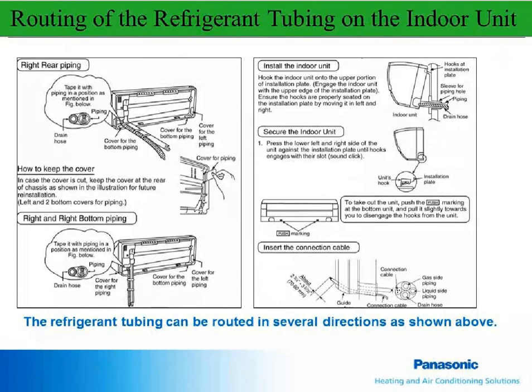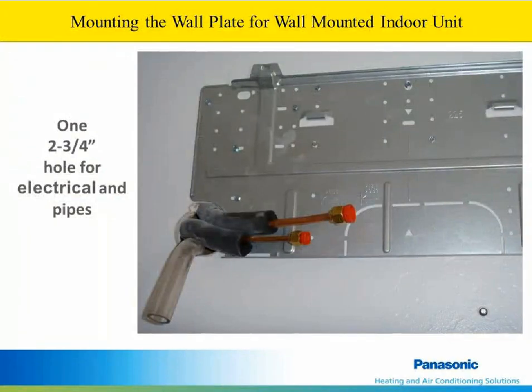If the line set will be ran in the wall, then routing into the back left side of the unit would probably be best. After hanging the unit on the wall plate bracket, you could tilt or move the bottom of the unit away from the wall, and the flare nuts could be tightened or leak checked. This example shows the line set coming into the left and back side. You can also see how the unit will hang on the top of the wall plate bracket and still allow access to the line connectors.